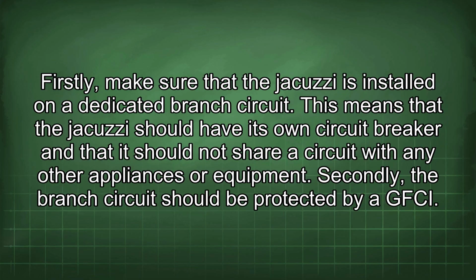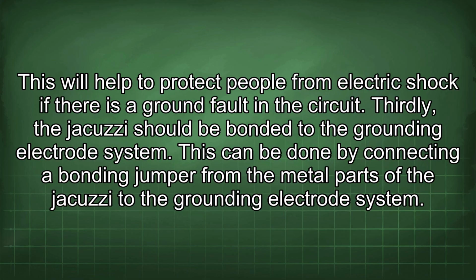Firstly, make sure that the jacuzzi is installed on a dedicated branch circuit. This means that the jacuzzi should have its own circuit breaker and that it should not share a circuit with any other appliances or equipment. Secondly, the branch circuit should be protected by a GFCI. This will help to protect people from electric shock if there is a ground fault in the circuit.